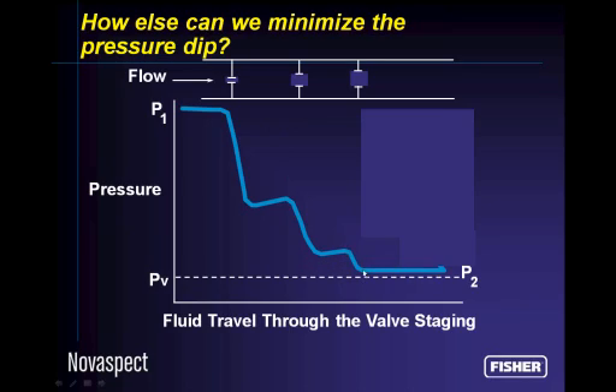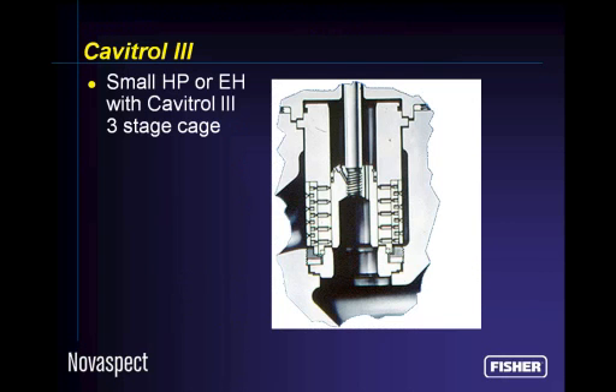If I did that enough times, I might reduce the probability that this last dip drops below the vapor pressure, and therefore I would reduce the propensity of this valve to want to cavitate. In essence, all valve manufacturers do this by creating a series of pressure drops through their control valves, creating a whole bunch of orifices in one example that are all in series, and each one has a recovery zone around it. You can see that the flow rate comes through the little orifices and then bigger orifices and then even bigger orifices.